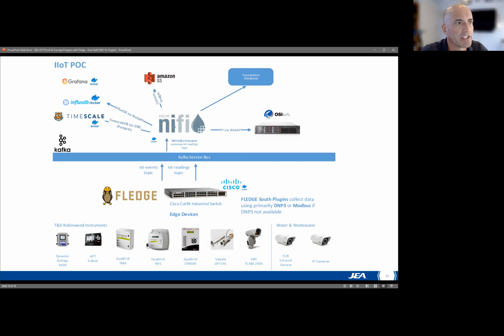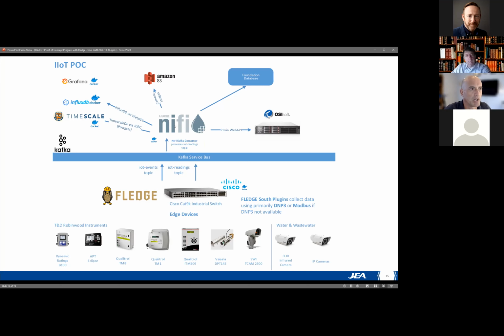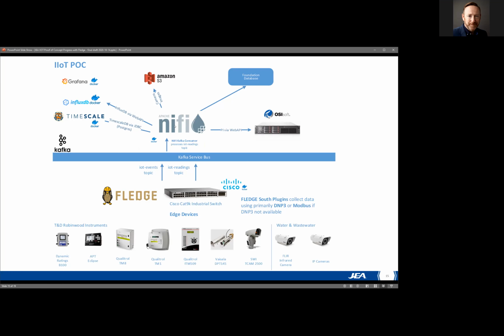Upstream, we're using a North plugin to shoot data into a Kafka service bus. Kafka is something new we're doing, and we're not only shooting the data we're reading, but also any events we're generating by looking at the data. From there, we're putting it into an OSI Soft historian that we've had for a long time. The Kafka service bus basically allows us to publish to it, and then we can create whatever subscribers we want. We're also looking at some other time series databases for less important data, and we have things like camera images that we want to collect and put into S3 storage so we can train models and try to do detection.